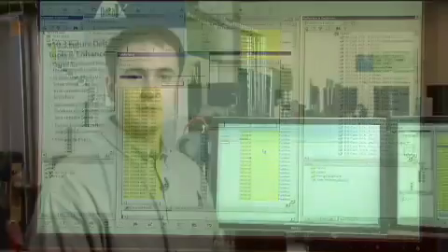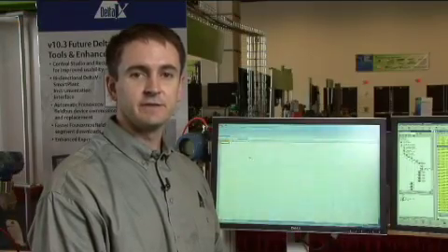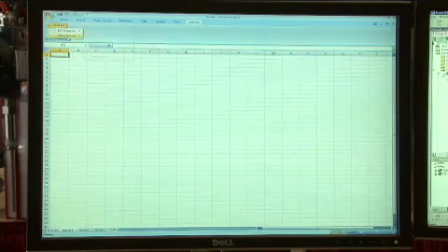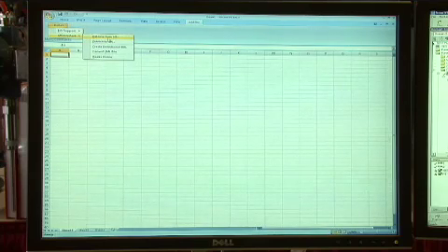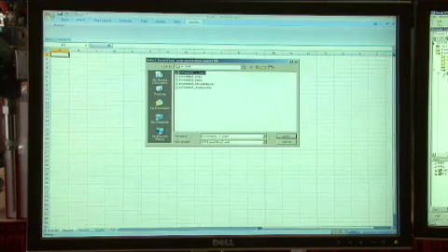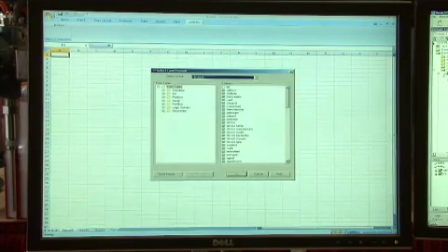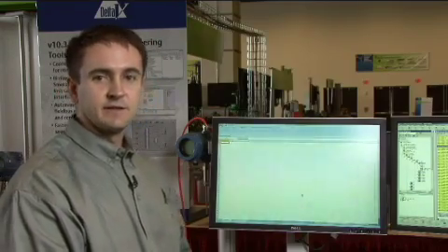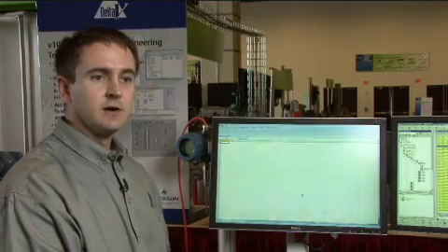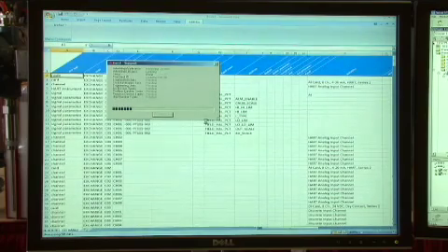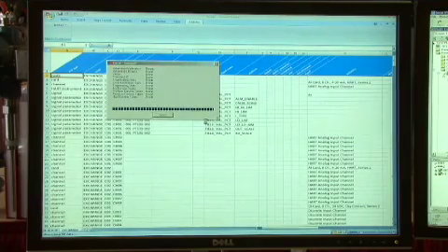Now that I've successfully published the SPI configuration of my DeltaV system in an XML file format, I will pick up that file and then transfer it into the DeltaV database using an Excel add-in that comes with the DeltaV software. I'll quickly demonstrate these steps now. Now that I have set off this process, I can bring in the data into the Excel spreadsheet, and I can show all the data that was configured within the SPI software. I can perform data reconciliation checks and validation before I publish and save this data into the DeltaV database.